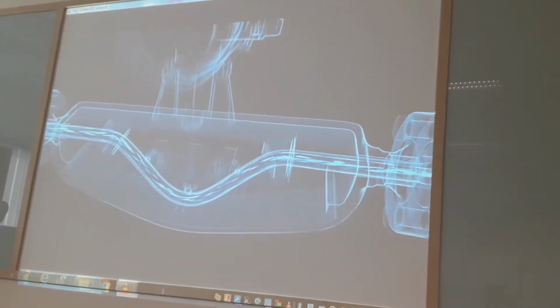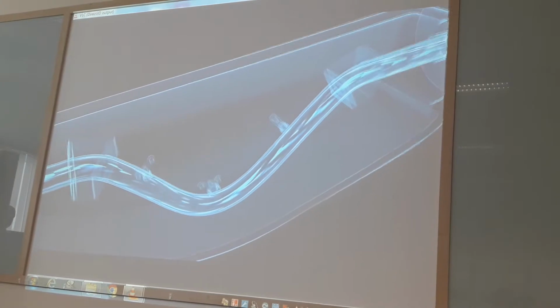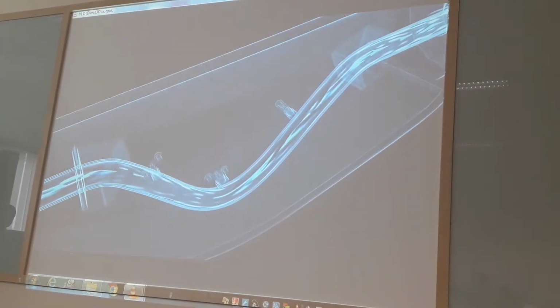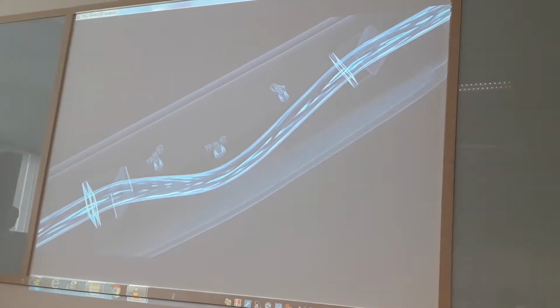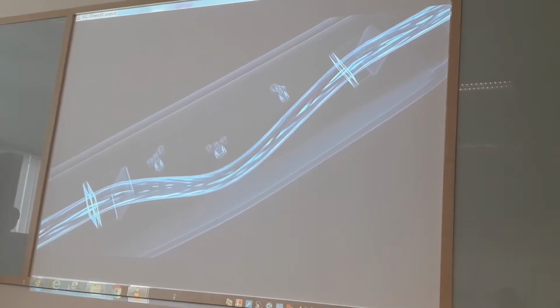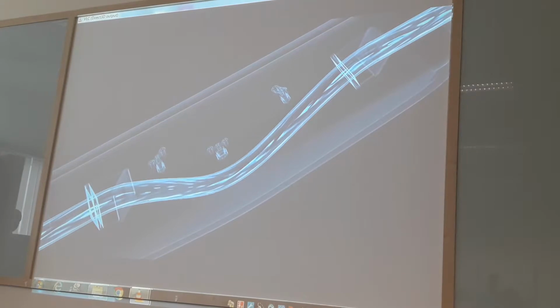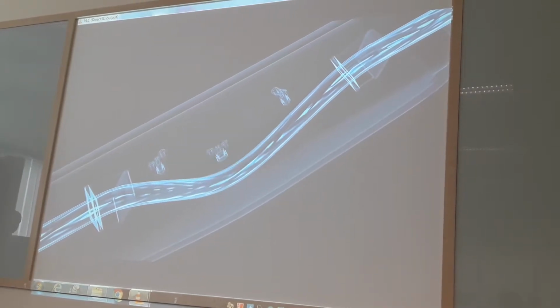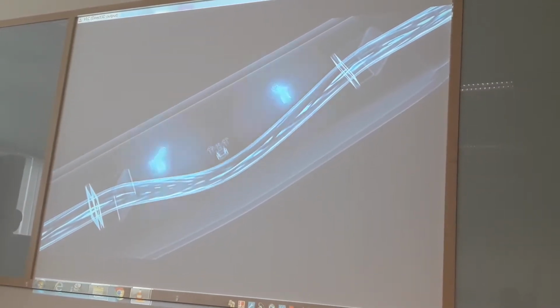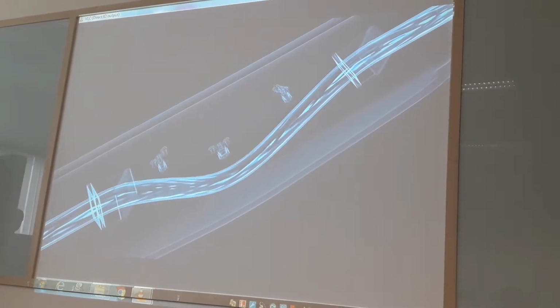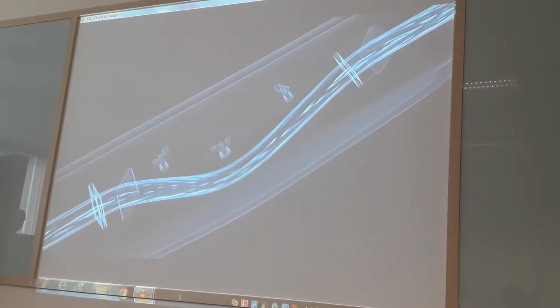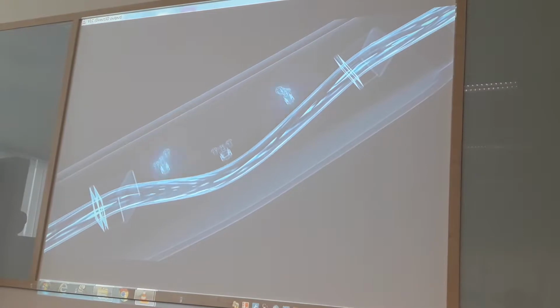The tube is located inside each Coriolis flow meter. An exciter causes this tube to oscillate constantly, here in an exaggerated example. If there is no flow, the measuring tube oscillates uniformly. Sensors are located at the inlet and outlet and register this basic oscillation precisely.